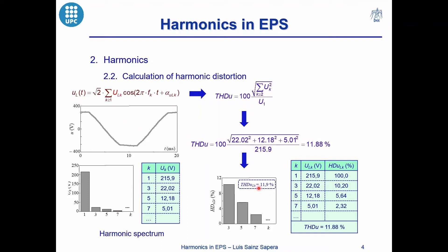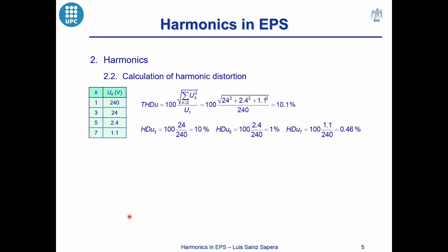In the next screen I will justify the necessity of both indexes. Imagine that we have a voltage waveform with a given data set and we determine the distortions of the waveform. The total harmonic distortion shows that the waveform is highly distorted, and the individual harmonic distortion indicates where the origin of this distortion is. So this voltage is a globally distorted waveform due to the third harmonic distortion.